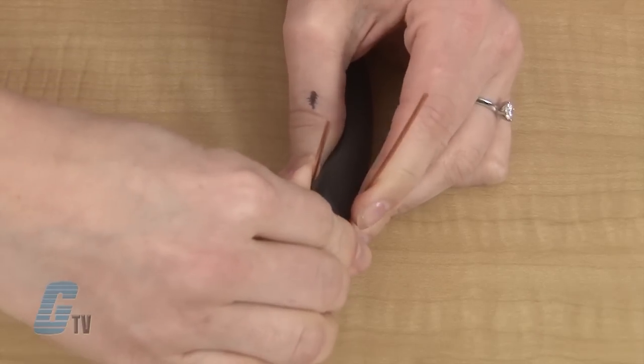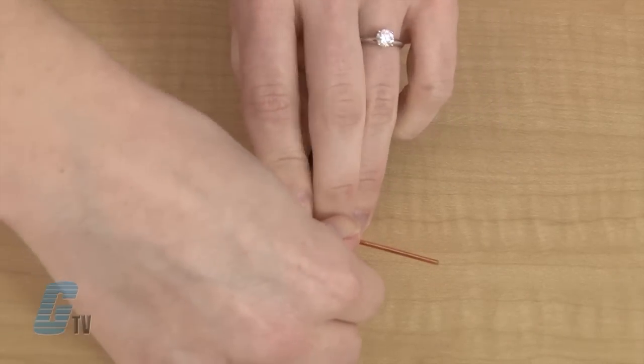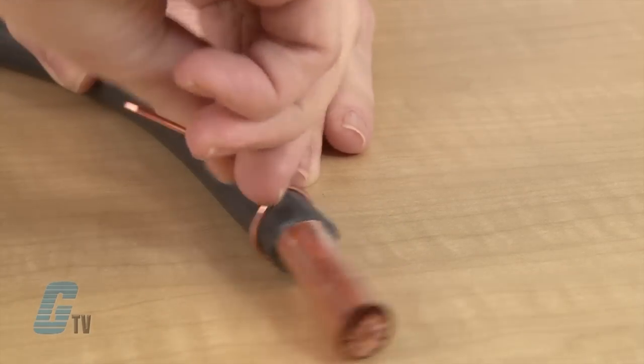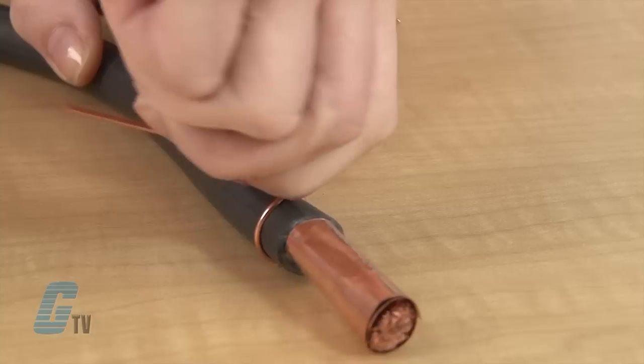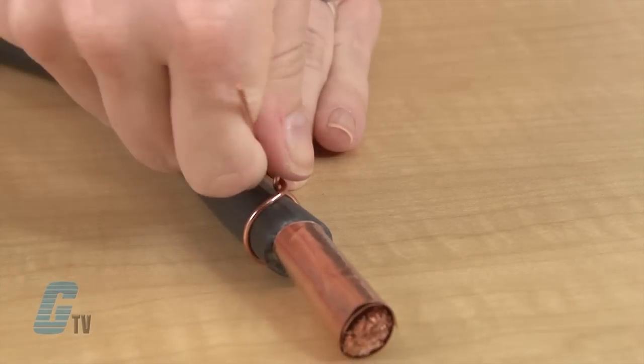After the cable is wrapped with the shim, I can wrap the strain relief clamp on the insulated portion of the cable and then twist it tightly about three to four times, ensuring the wire bites into the cable and then a few more loose turns.